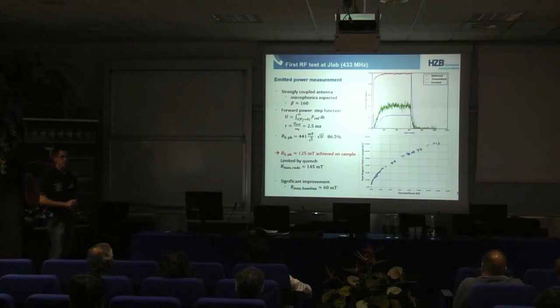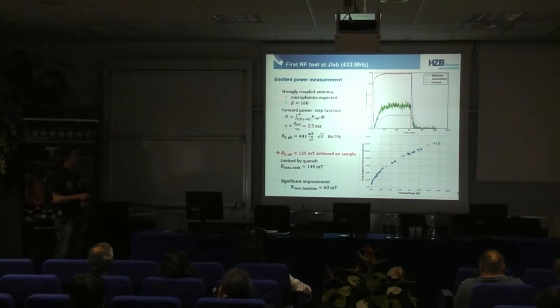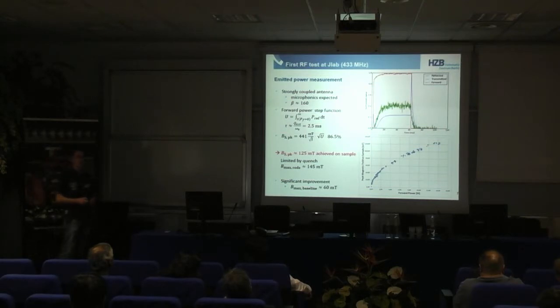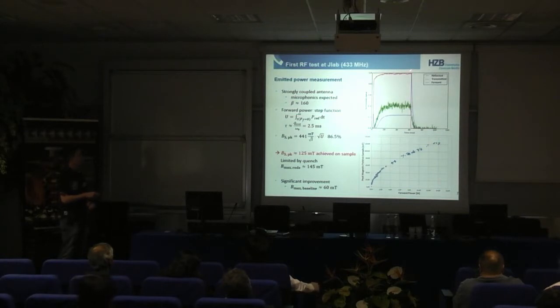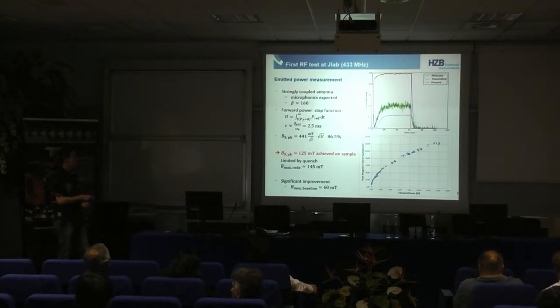First RF measurements have been done at JLAB just recently. We wanted to measure the stored energy inside of the cavity via an emitted power measurement. We have a strongly coupled antenna — a fundamental power coupler with a beta of around 160 because of expected microphonics — which broadens the resonance peak and makes life easier for the RF system. We have in red the forward power of the RF system as a step function, and we switch off the power. The stored energy from inside of the cavity comes out through the input coupler and we see this exponential decay.